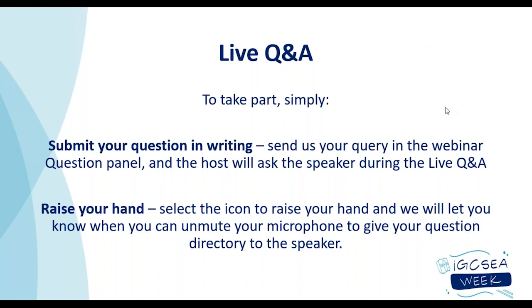Thank you. Another question here: the experiment with high temperature is above the boiling point of some probe molecules like cyclohexane, toluene. Does this cause any issues when it comes to vapor injection? No, we inject everything in a vapor phase. IGC SEA has vapor phase injections, like a headspace injection for analytical GC. So we already inject everything in vapor phase, and the injector port doesn't affect the injections.